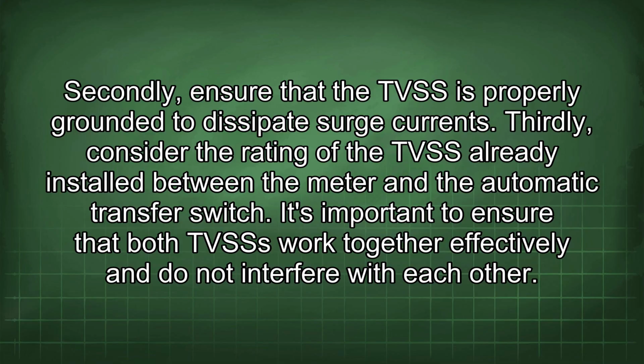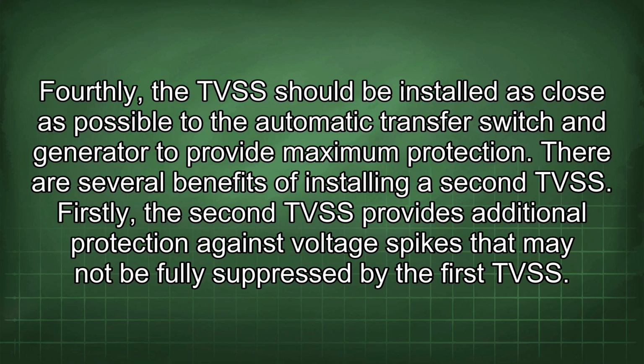Thirdly, consider the rating of the TVSS already installed between the meter and the automatic transfer switch. It's important to ensure that both TVSSs work together effectively and do not interfere with each other. Fourthly, the TVSS should be installed as close as possible to the automatic transfer switch and generator to provide maximum protection.